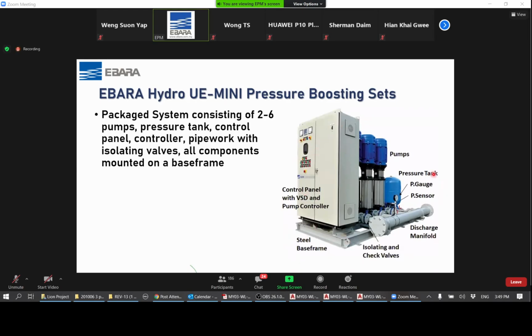So what does a booster set like our Ebara UE Mini package look like? As you can see from the picture here, a setup can consist of anything from 2 to 6 pumps. In this case, it's a 3-pump system built as a system with full accessories. You have a dedicated control panel housing all the electrical starters and VSDs, the suction and discharge pipework complete with all the check valves and isolating valves, a small diaphragm tank to absorb the pressure fluctuation, a pressure sensor here, and other standard accessories, even pressure gauges for the suction and the discharge. All these components are mounted on a steel base frame so that it is easy to install, just connecting the suction and the discharge from the tank to the outlet.